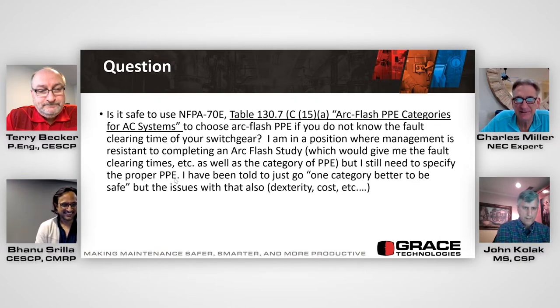I personally don't want people trying to do calculations on the electrical system, estimating fault current and clearing times, because often they won't know how to use that information or they'll miscalculate it. For example, if you take an infinite bus—it's kind of a lazy engineer's way to do this—it actually won't necessarily give you the maximum incident energy. You have to model the system for what's actually there rather than coming up with numbers you pull out of the air. So either use the table method or have a full engineering study, but don't be caught in the middle. There's a no-man's-land there and you'll end up with your pants around your ankles. My suggestion is you manage the hazards either through a real study or the table method—never the twain shall meet. Charlie, you can probably comment on this too.